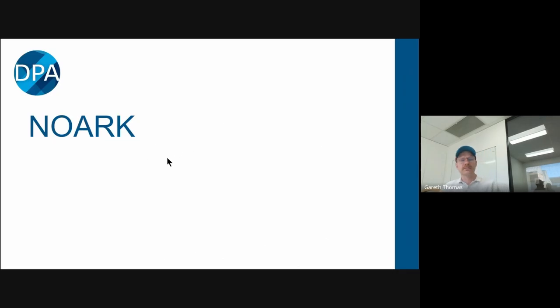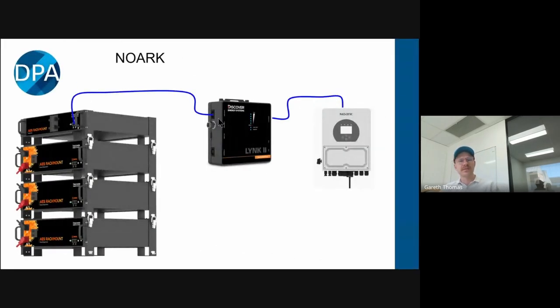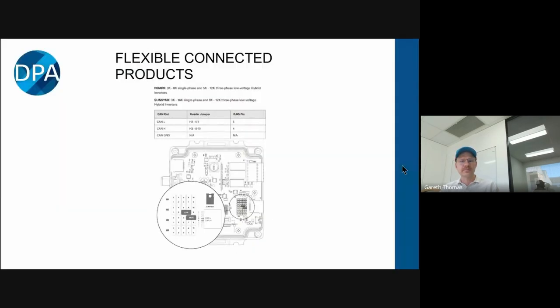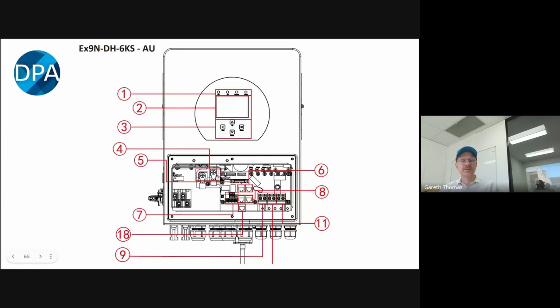So we'll do NOARK. NOARK is the same thing—you're going to go out of the top battery into your Discover LYNK, and then into the NOARK. You're going to set the CAN bus ports in the NOARK, and then go into the CAN bus port, which is here. As long as you've got the baud rate set correctly, you've selected NOARK in the link device, and you've got the pins correct—which if it just comes standard, you just use a normal Cat5 cable—you put it in there, and it's just going to show up straight away.